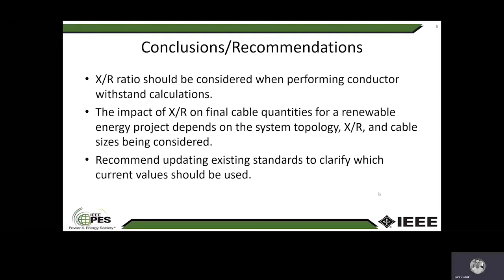But I do recommend that the ICEA standards be updated to clarify which current value should be used in order to truly account for the thermal loading which a conductor could experience during a short circuit event.